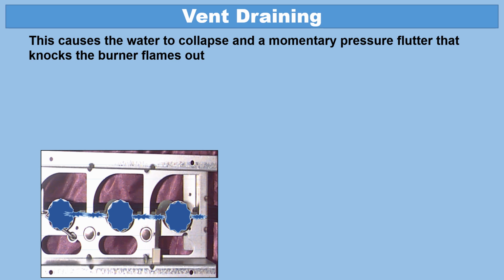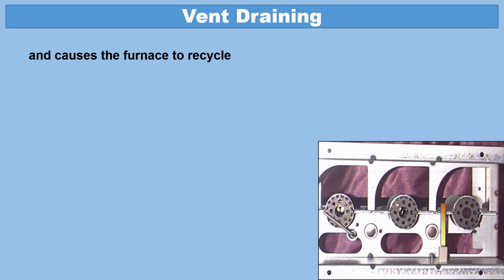So this causes the water to collapse, and that momentary pressure flutter that knocks the burner flames out. It's going to knock it out, but it's also going to recycle and immediately light again. And then it's going to happen again when you get enough water built up. It's going to happen again. If it happens 3 times in one cycle, you'll go into a 1 hour soft lockout.